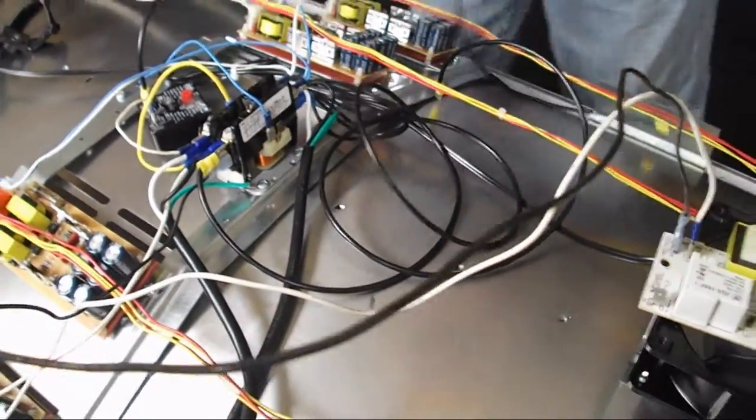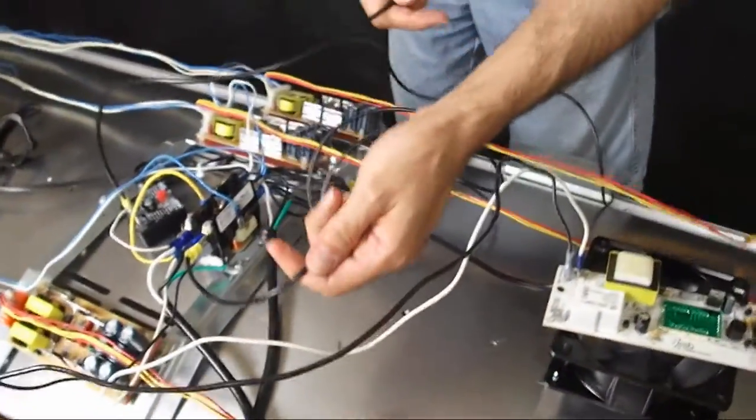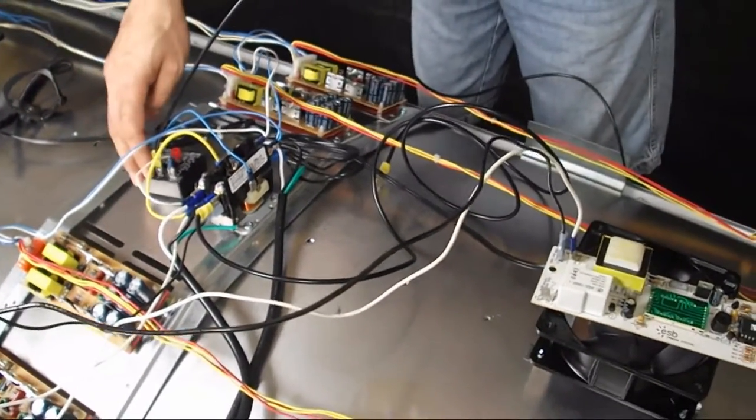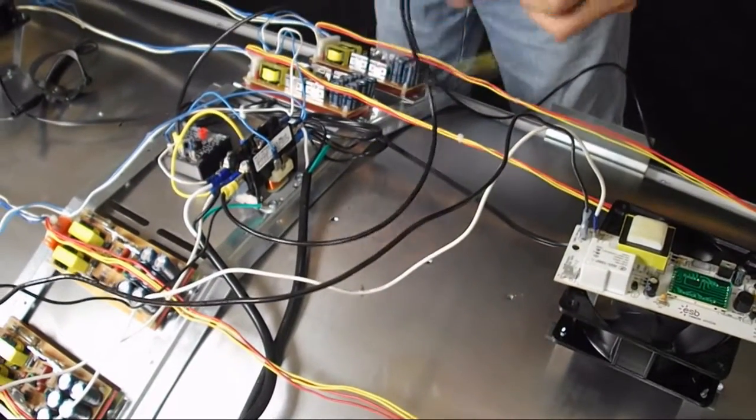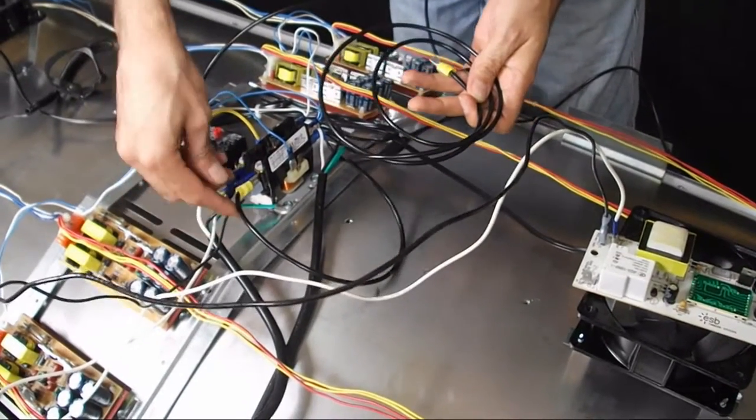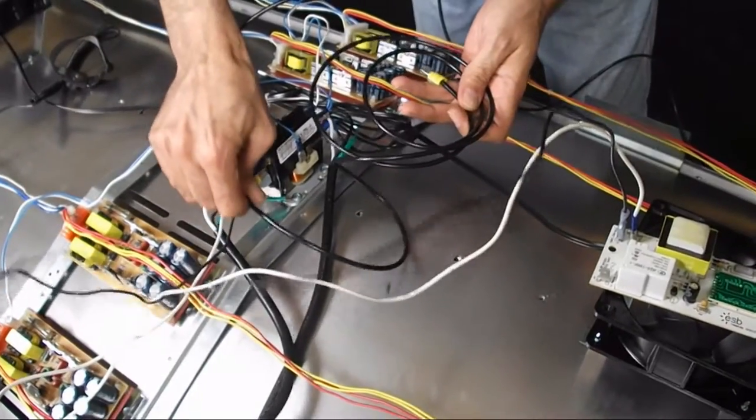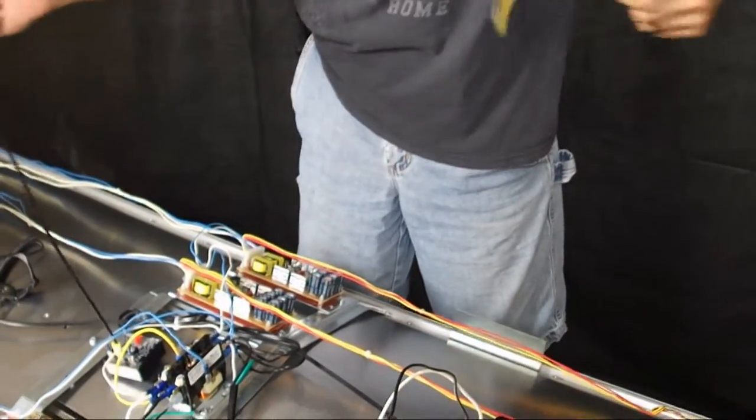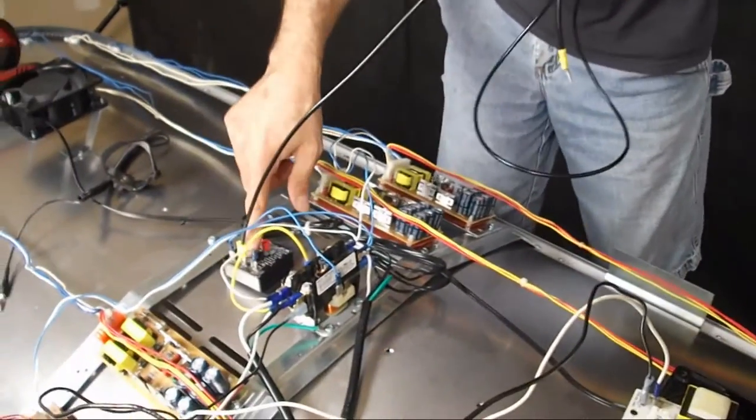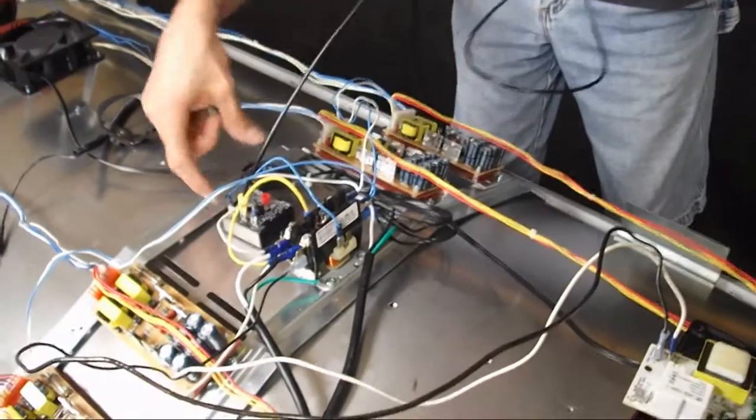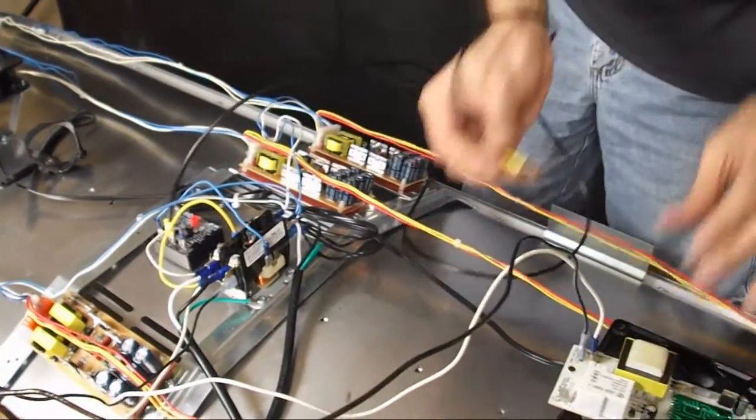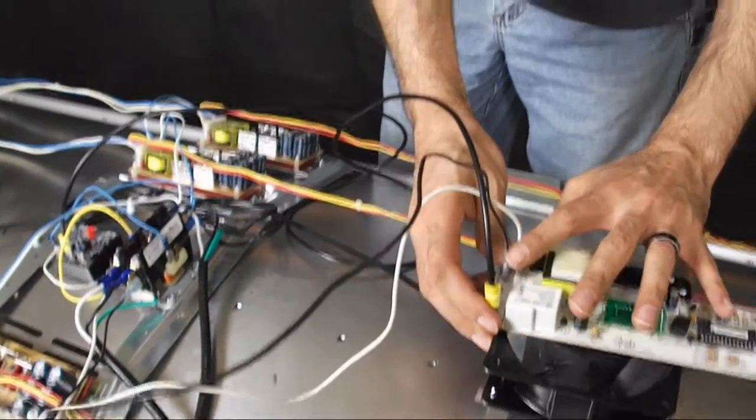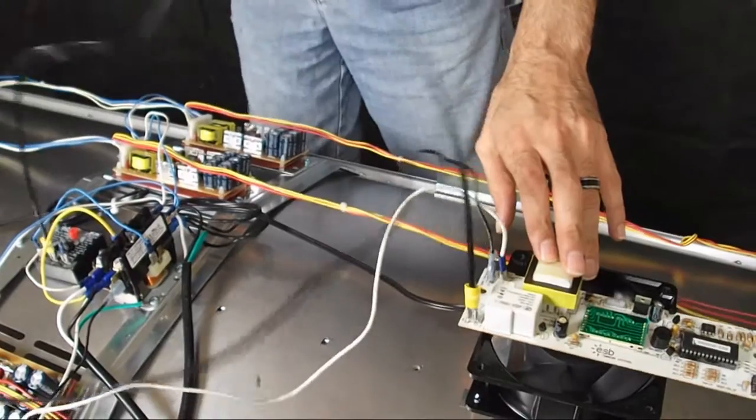Now, we have two black wires here left. One goes back to the primary of the contactor, and one goes to the backup timer. Now, on some models, and with the Borg timers, you might not have a backup timer. I'll address that in one second. Basically, though, this wire here, this redundant hot wire on the primary of the contactor, I'm going to remove. I'm going to disconnect it, and we're no longer going to use that. I'm going to actually just discard that one. So, again, this is the wire that we're going to use. It goes to the backup timer on the input terminal. Actually, it's marked A1 and 1. This goes to J6 on the main timer here. And now, it's completely wired. That's proper, just like it is.